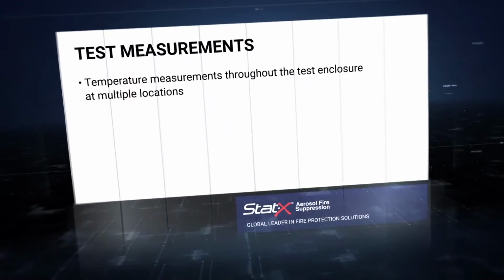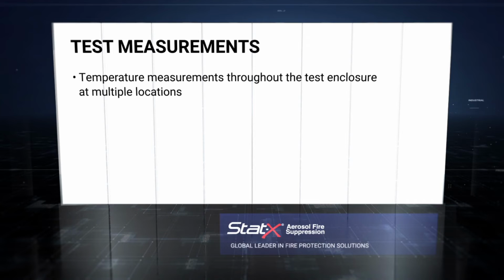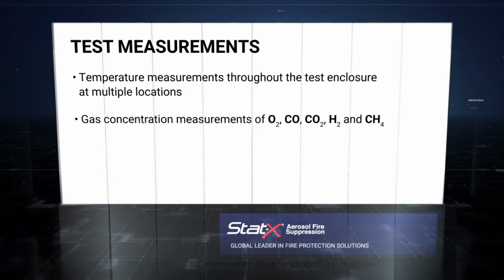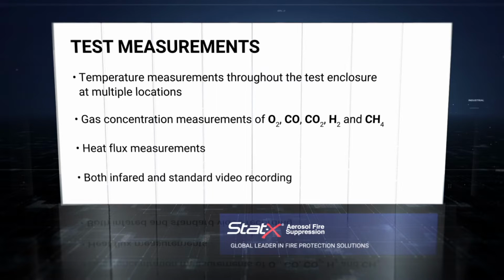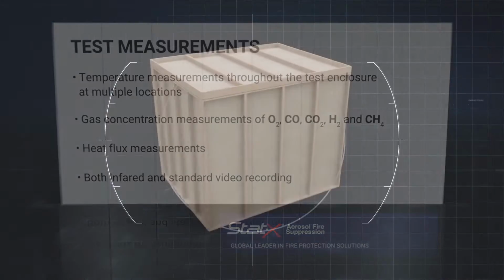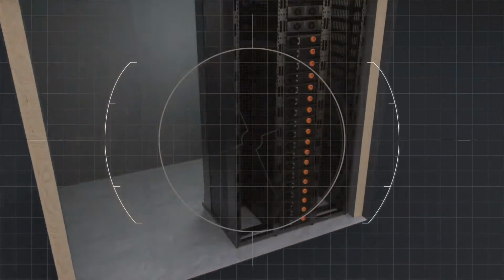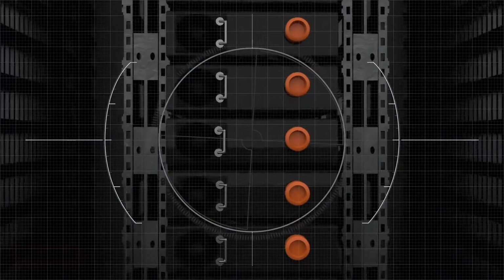The desired data from the test included temperature measurements throughout the test enclosure at multiple locations, gas concentration measurements of oxygen, carbon monoxide, carbon dioxide, hydrogen, and methane, and heat flux measurements. Both infrared and standard video recording were also obtained. The test began with overheating a single lithium-ion battery within the center rack.